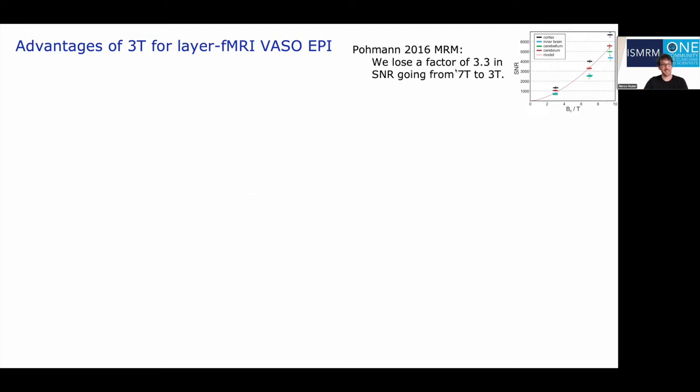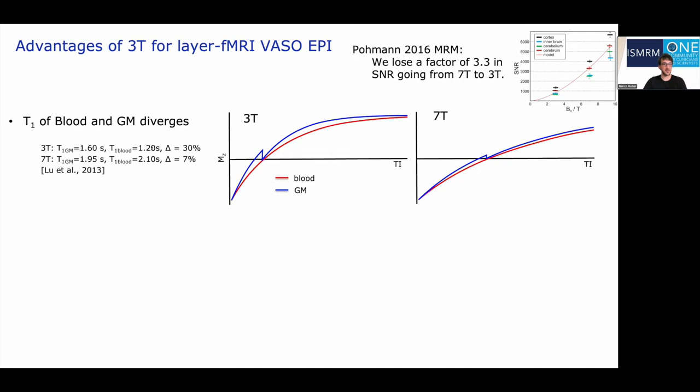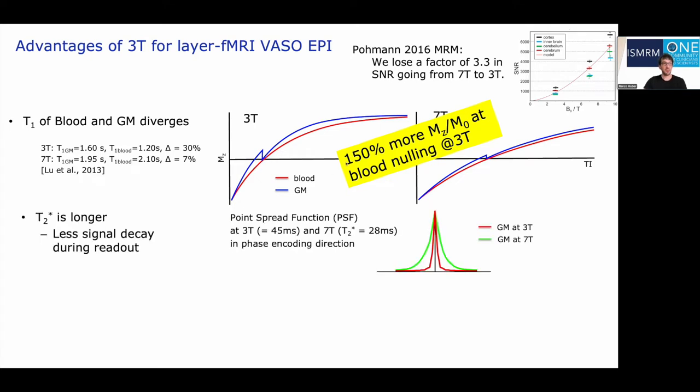While 7Tesla offers larger magnetizations and better contrast-to-noise ratios, 3Tesla also has some virtues, specifically for VASO fMRI. For example, the relative difference between blood T1 and tissue T1 increases from about 7% at 7Tesla to 30% at 3Tesla. VASO is an inversion-recovery sequence where we acquire images roughly at the blood nulling time, and a larger relative T1 difference at 3Tesla really boosts our available magnetization and signal by about 50%. Furthermore, T2* is longer at 3Tesla, meaning less signal decay with the large matrix sizes needed for sub-millimeter fMRI, and a sharper point spread function, giving maybe another 50% depending on the echo time.